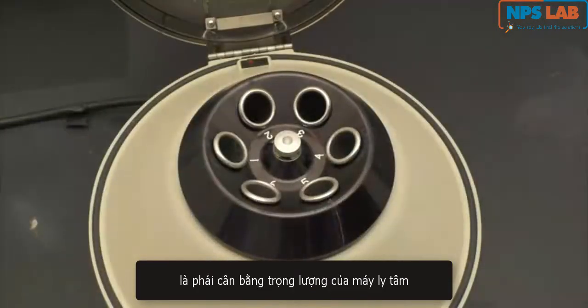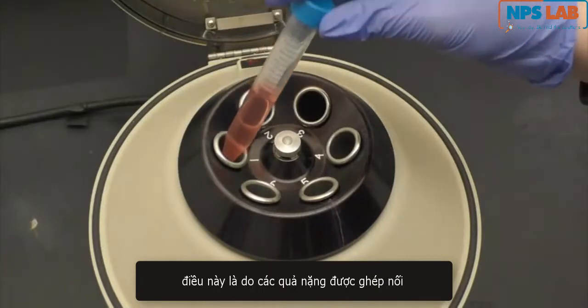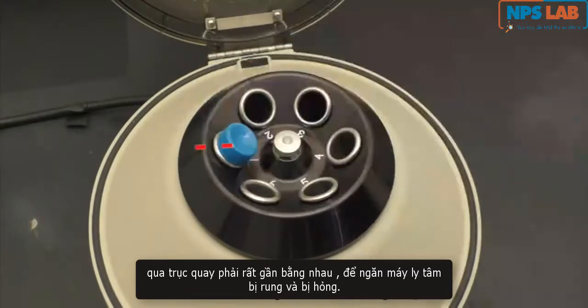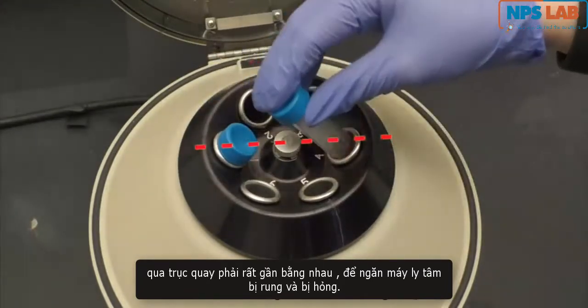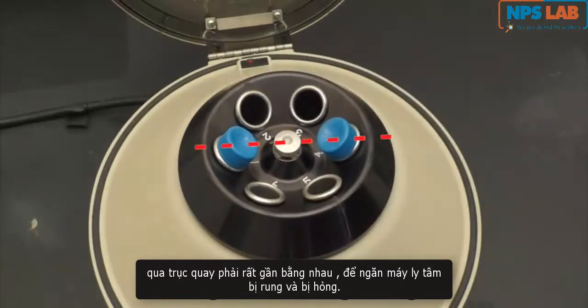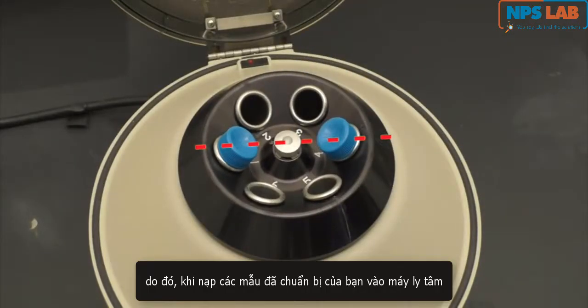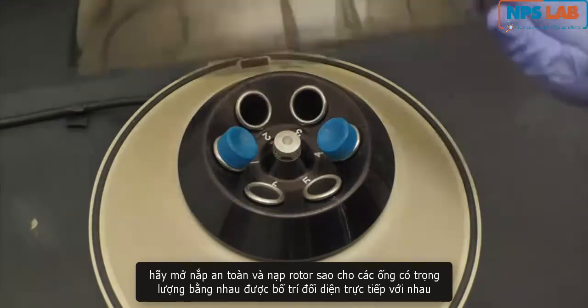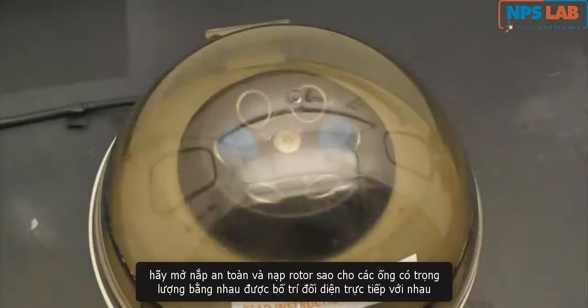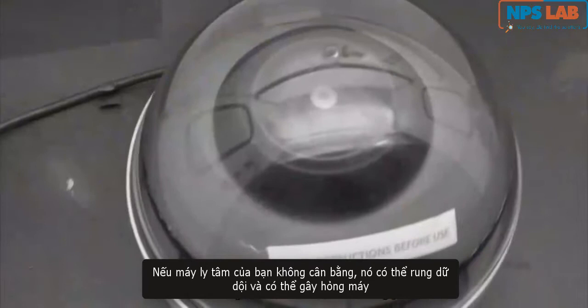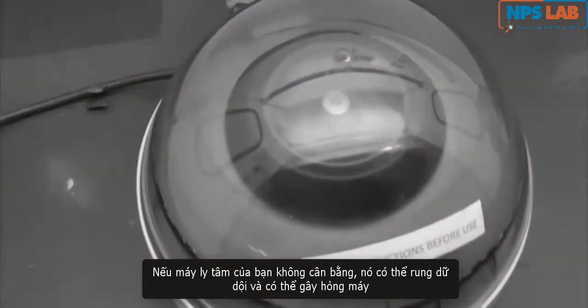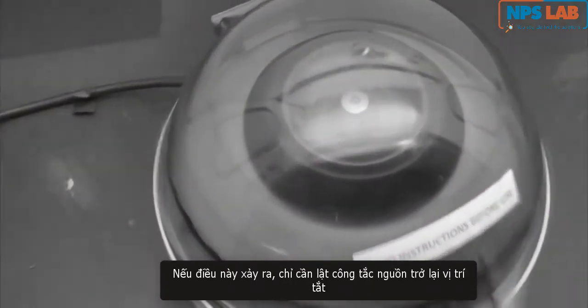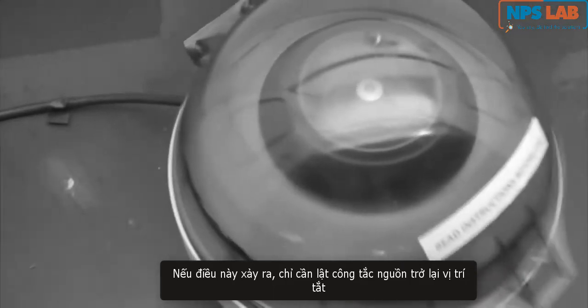When running a centrifuge, it is very important to balance the centrifuge by weight. This is because the weights paired across the rotational axis must be very close to equal to prevent the centrifuge from vibrating and becoming damaged. Therefore, when loading your prepared samples into the centrifuge, open the lid and load the rotor such that tubes of equal weight are arranged directly opposite one another. If your centrifuge is unbalanced, it may vibrate violently and could cause damage to the machine. If this happens, simply flip the power switch back into the off position.